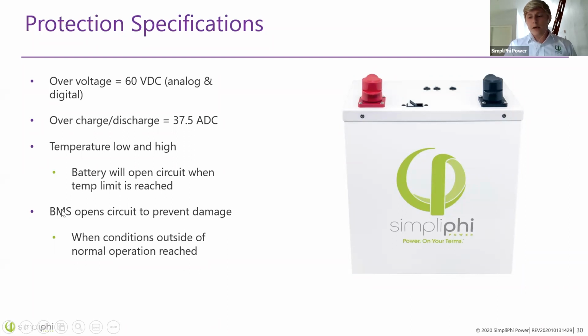So I want to bring up one point here: the BMS is not some magical unicorn that's going to allow you to plug your battery into a wall and just use 120 volt power or something crazy to charge your battery. You still need to treat the battery how it needs to be treated. However, the BMS is there as a line of defense. It's not the only line of defense, right? So the system still needs to be designed properly and sized properly. A BMS does not modify the voltage of the power going in or out or the current. It's just going to essentially open the circuit and stop providing power if it doesn't like what it sees. We did a very detailed training on BMSs, so if you need to find that, just email me.